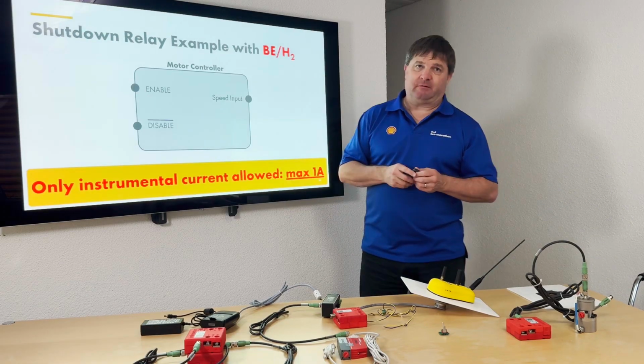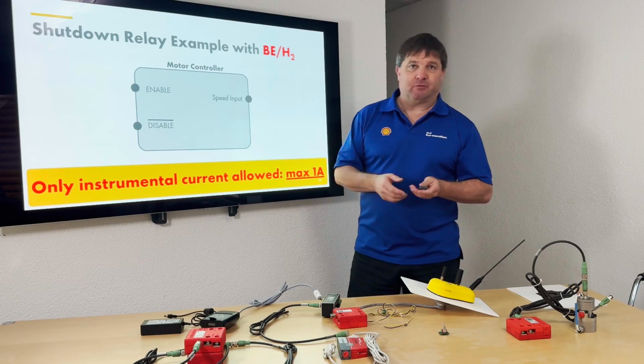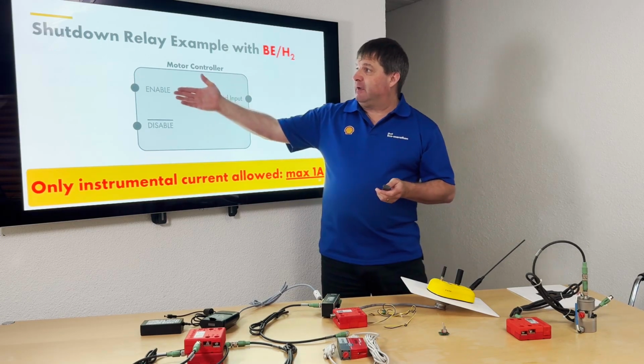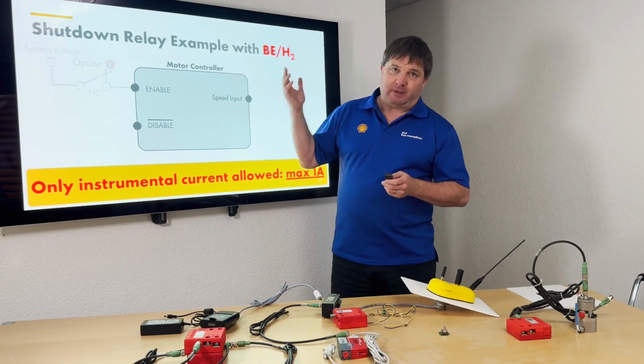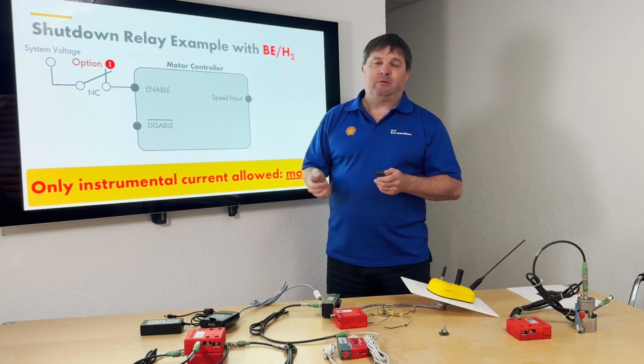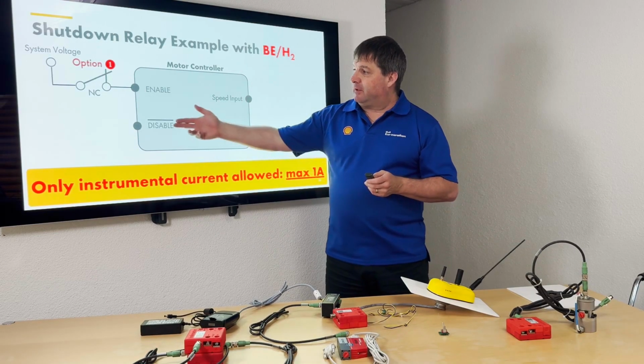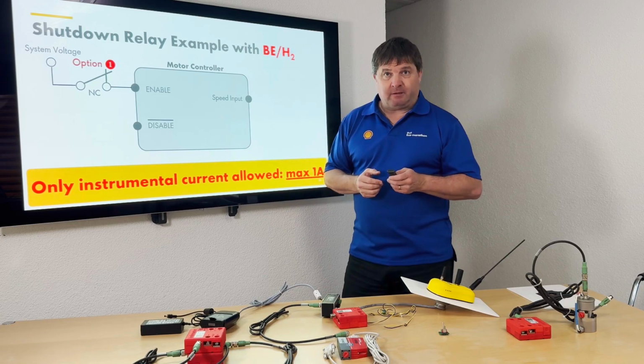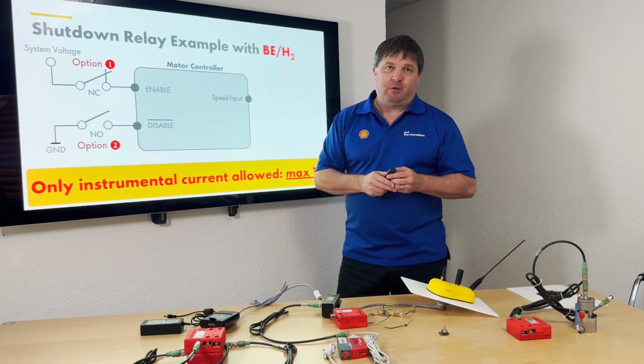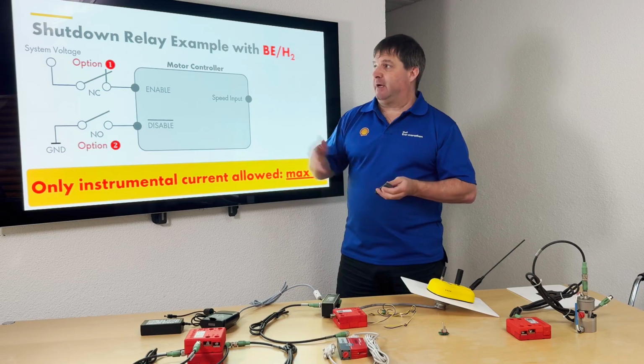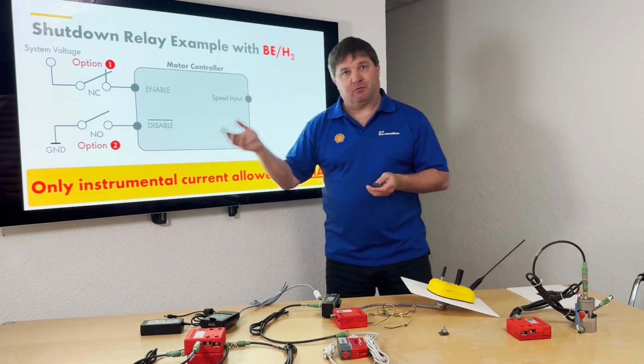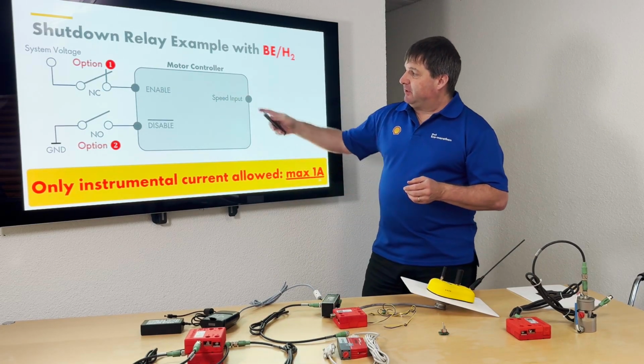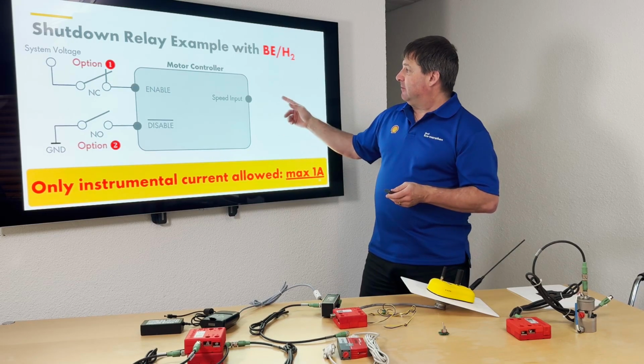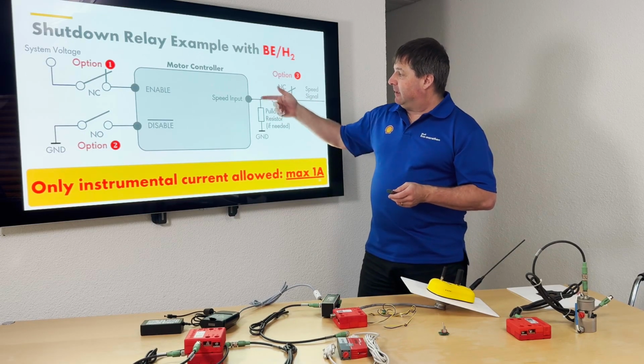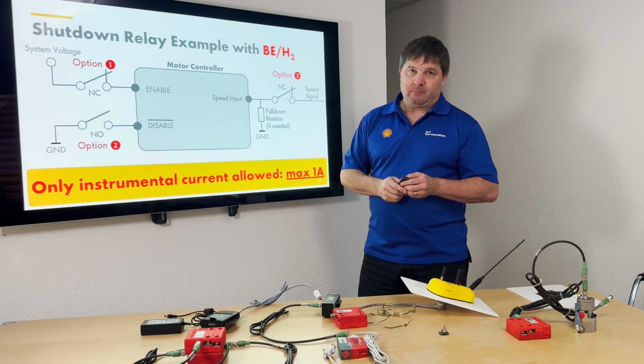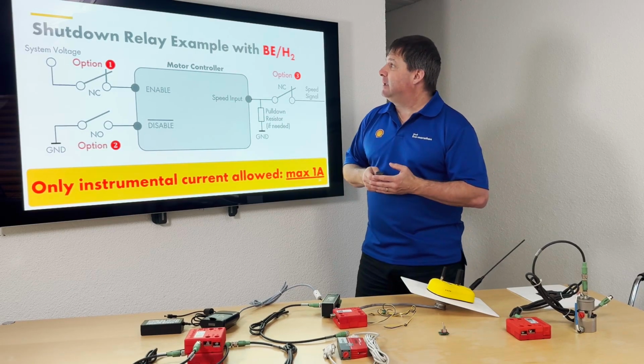Let's start with battery electric and hydrogen, because they have a motor controller for sure. For example, we have an enable input, so we use a normally closed relay and pull the signal to the system voltage. Or you can use disable negative and pull it to ground with a normally open contact. So in either case, when the relay fires, the motor stops. Or you can use the speed input and disconnect it with a normally closed relay and then use a pull-down resistor. So this is one example.